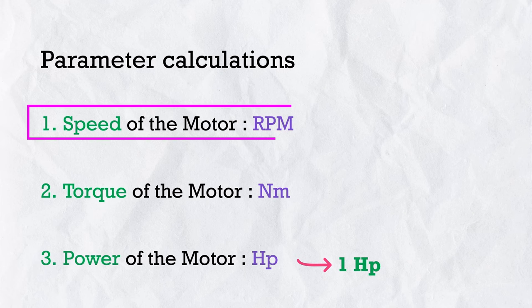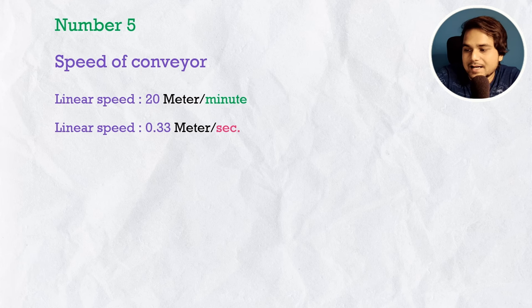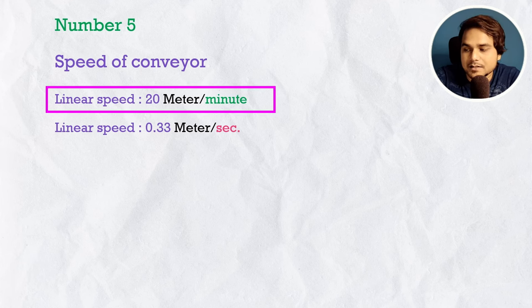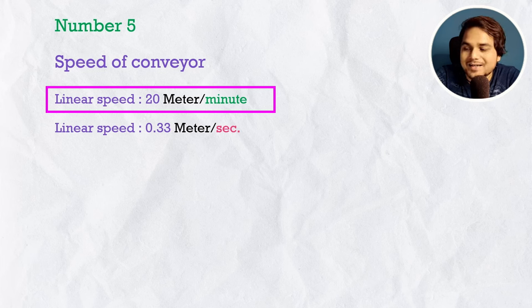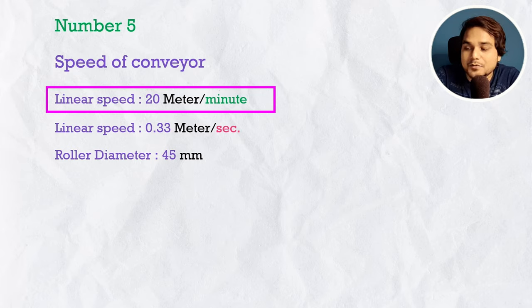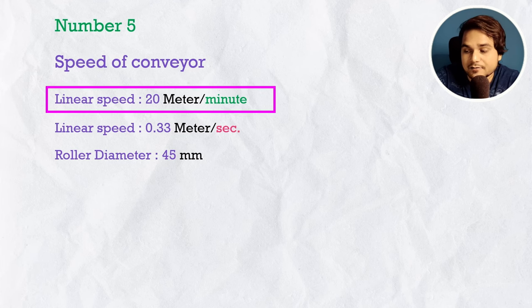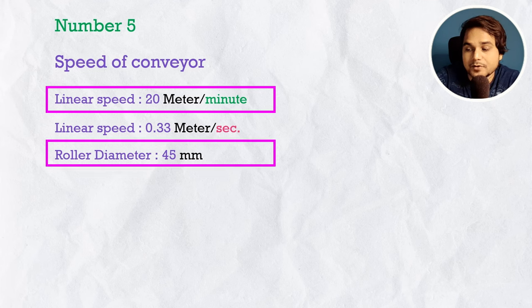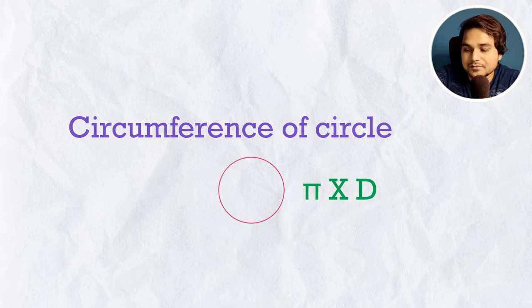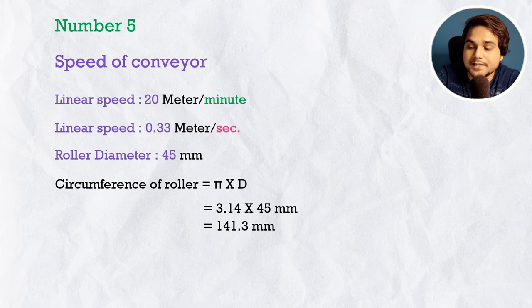Now we must calculate the rotational speed of the motor in RPM, because motors come with different combinations of speed and torque for the same horsepower. We have the belt linear speed of 20 m/min and need to convert it to rotary speed. For that we need the driving roller diameter — for example, 45 mm. First, calculate the roller circumference: π × d = 141.3 mm = 0.1413 m.